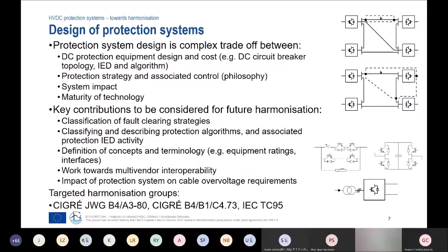The next topic, application and specification of HVDC circuit breakers. Depending on the application and, for example, the protection strategy, the grounding and the faults which you would protect against in a protection system, there are quite different requirements on the HVDC circuit breaker.